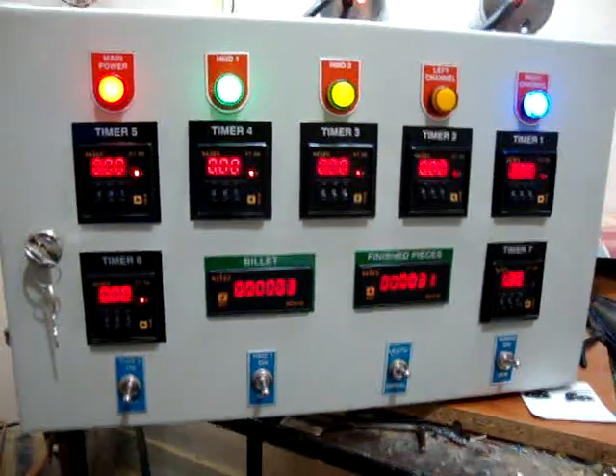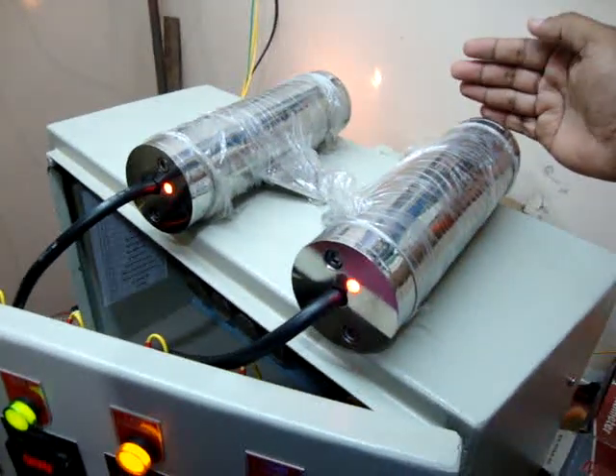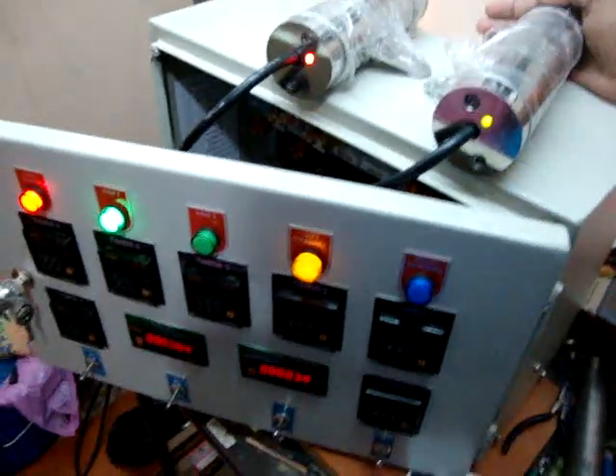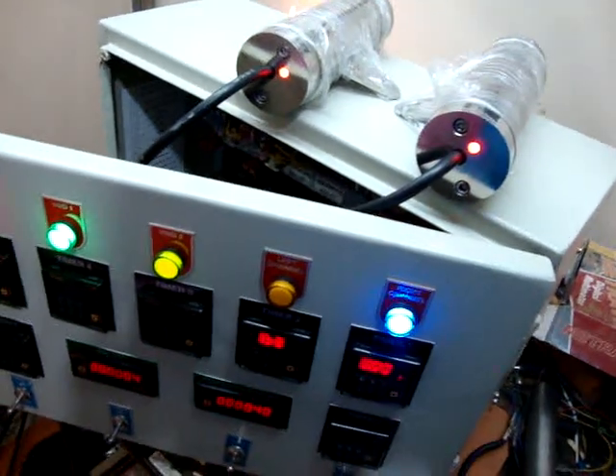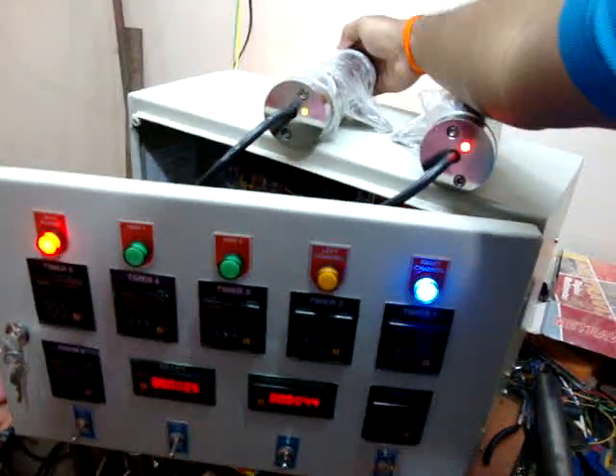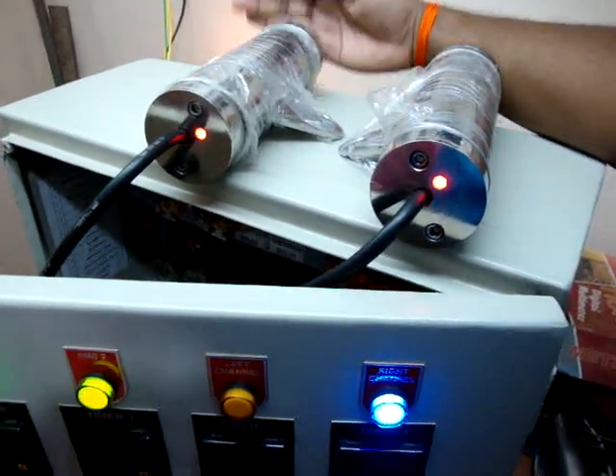Now I can break this process with the help of the sensors. They will turn off if I close them. You can see it's green now — that's power on mode, but there is no hot metal in front of the sensors. If I leave it open, it starts again. If any one sensor goes off, I can block it and the process stops. Even if I block the second one and leave, the process does not resume.